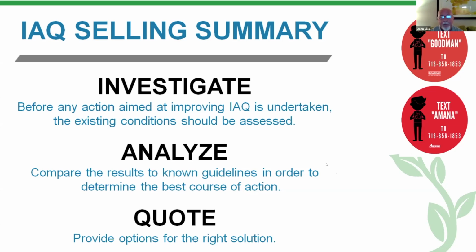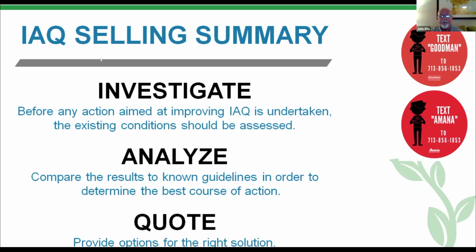Obviously, if you have carbon monoxide, that's going to put off some red lights. That would take you to look at your combustion products within the home, your combustion air zone. So you follow the data, analyze it, and it's going to point you in that direction. You need to have a look at your combustion appliances. Are they venting properly? Do we have clean burns in our combustion appliances? And again, that could point to building pressures. If we've got a structure that's slightly negative in building pressure and we're causing certain appliances to backdraft, that's going to point you right there, and you could take care of that problem.